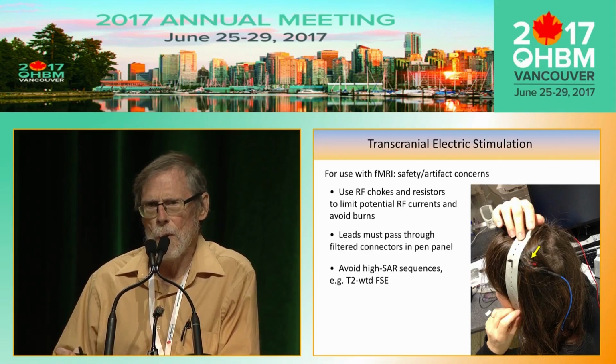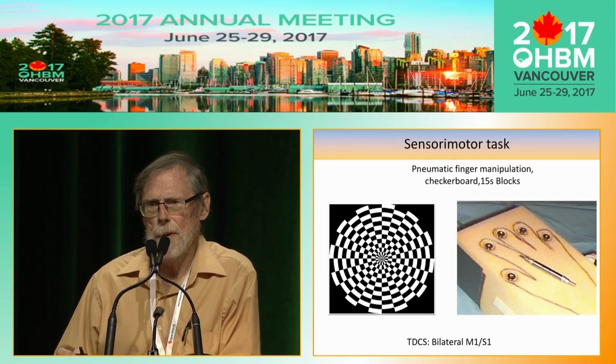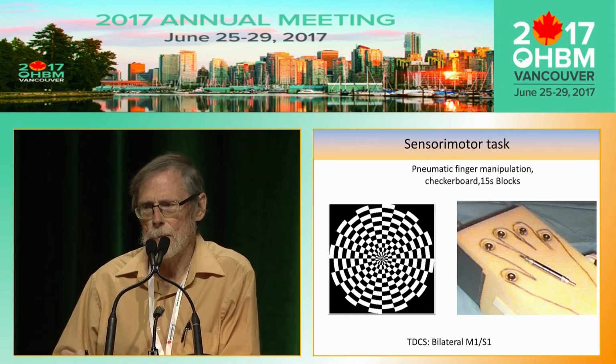And you also have to worry about high SAR, a large deposition of RF, when you're doing these kinds of things in a magnet. But those can be performed.